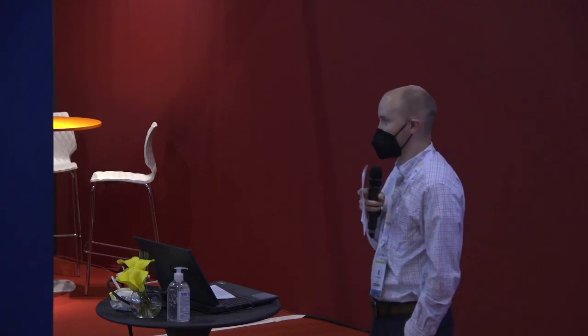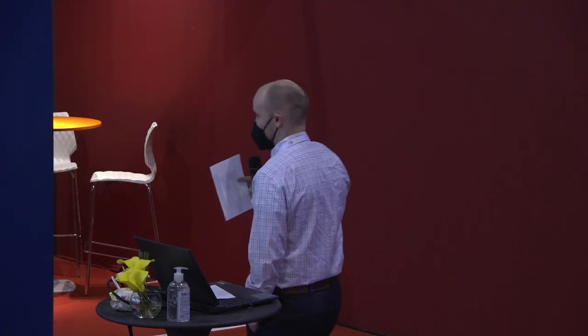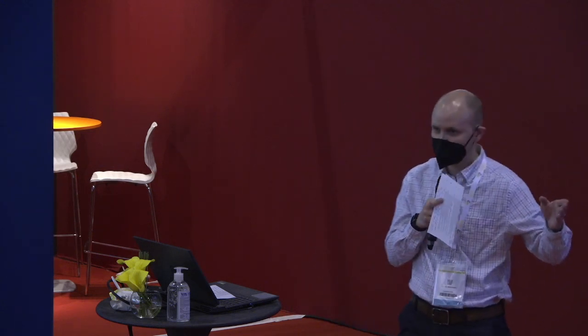And the plants that have those are using them to do alternative treatments, to be able to treat components that were classified as safety, but we know is low safety significant. They're able to classify those cheaper. They're able to procure parts for cheaper. They're able to focus their maintenance on the parts that are more important for safety and less on the ones that are not important for safety.